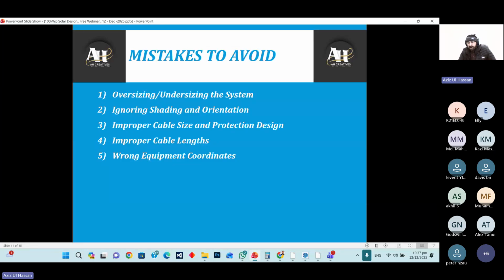Wrong equipment coordination: we have not properly designed the system. They have no coordination in between, like the inverter and MV station coordination and other equipment coordination that is not properly designed. They will cause a big impact in the future.